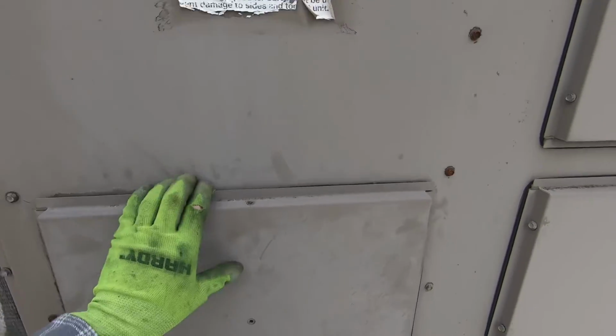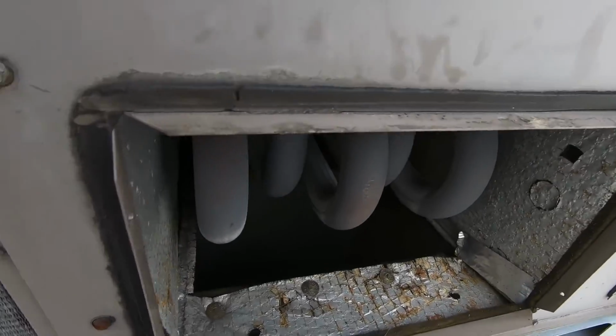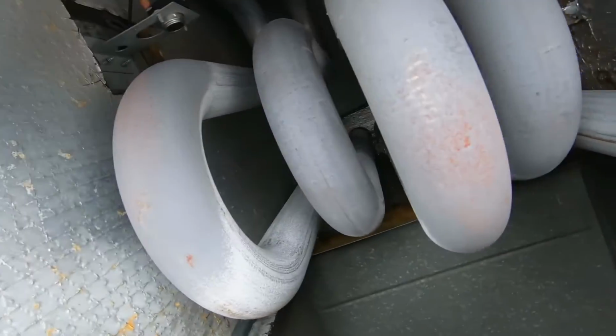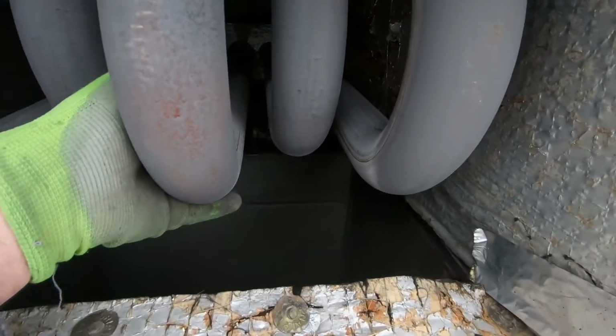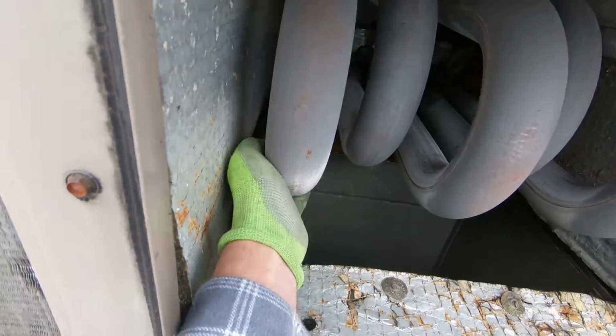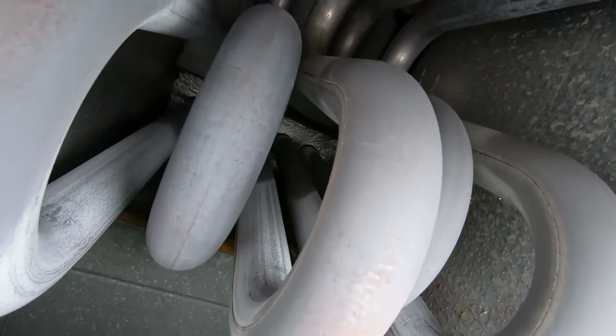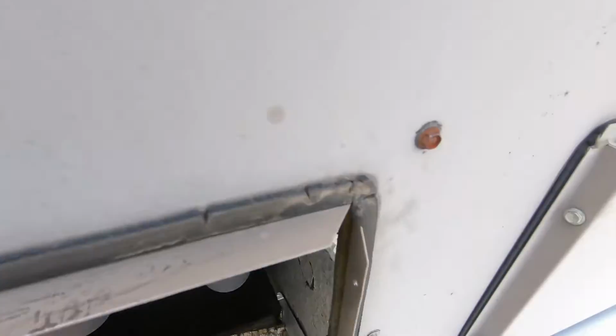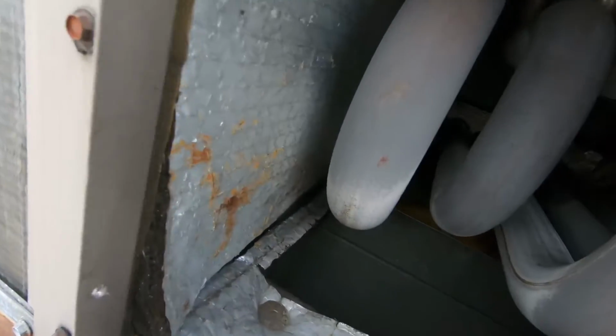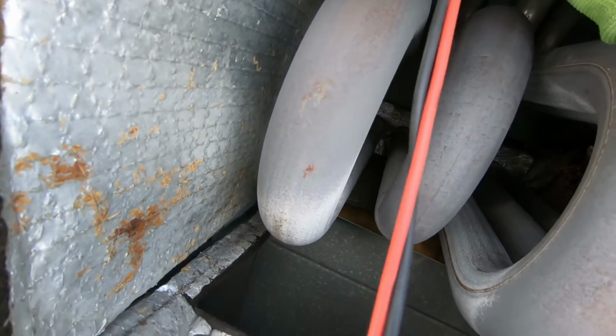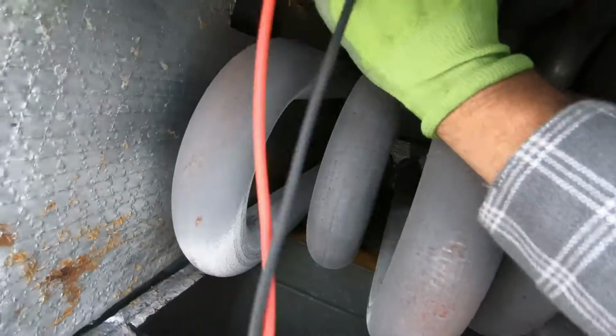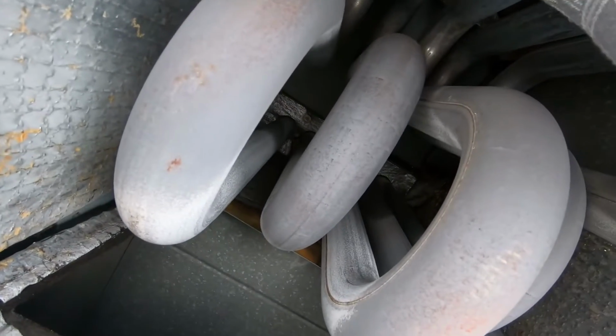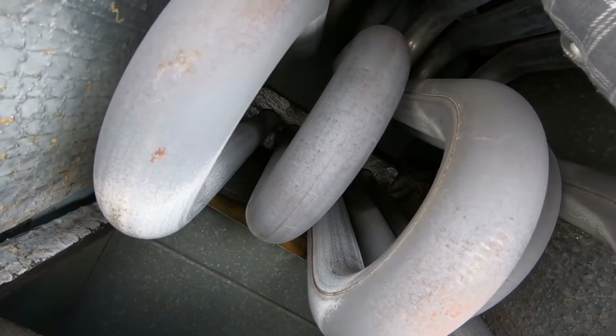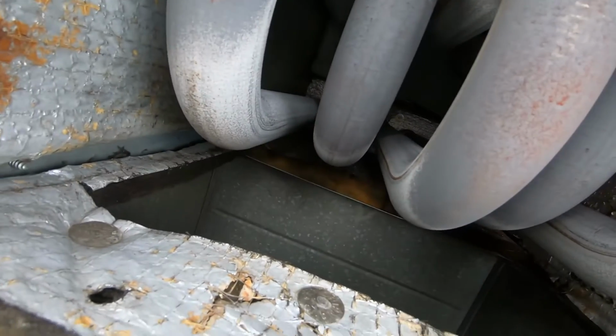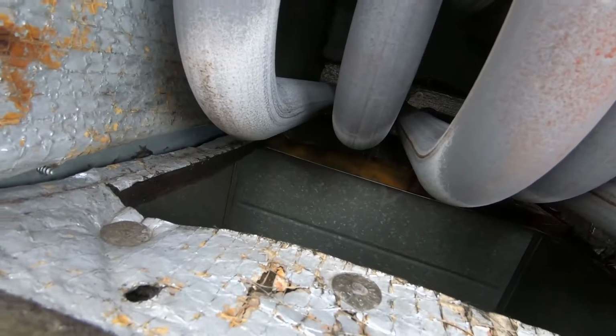Well, let's take a peek here. All right. Check that. These all look pretty decent. Not getting too in depth. I don't see any of the seams rotted out or anything like that. All right, guys, I checked the other limit inside here. We do have continuity. So I think we're in decent shape on all the limits, but what caused that thing to trip? We get these wires pushed back on and we're gonna reset it and see what it does.